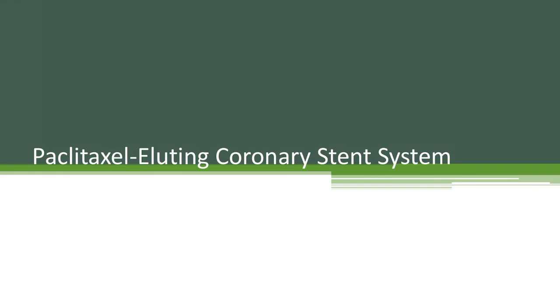Paclitaxel eluting coronary stent system consists of a balloon expandable Veriflex stent coated with paclitaxel in a slow release 8.8% formulation triblock copolymer system and pre-mounted on either the monorail or an over-the-wire delivery system.